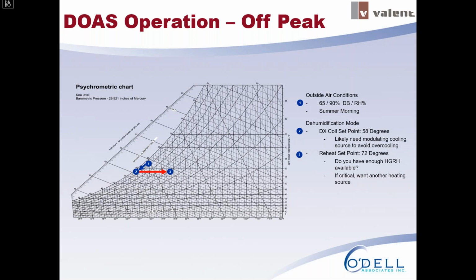The other consideration is you're going to want to reheat to some set point. You don't just want to supply cold, damp air into the space. You want to be able to reheat so you get that air back up to roughly room neutral. And to do that, we use hot gas reheat.